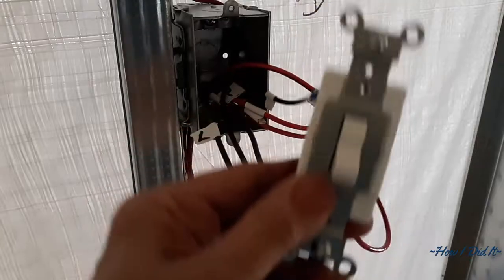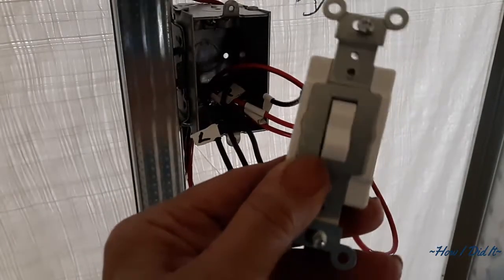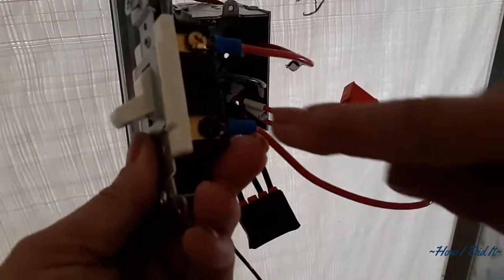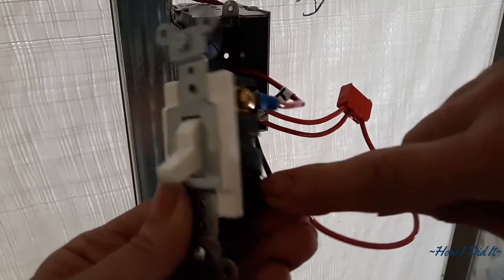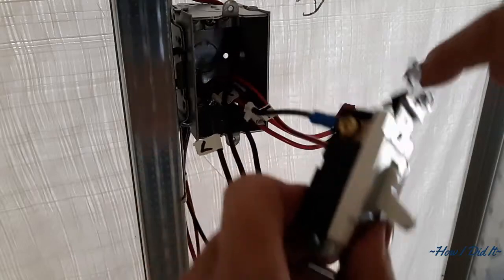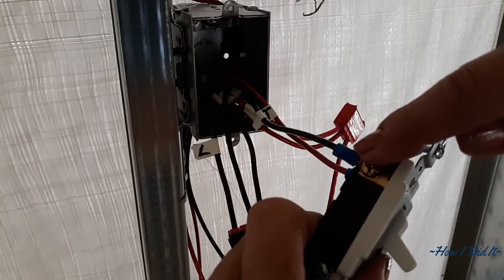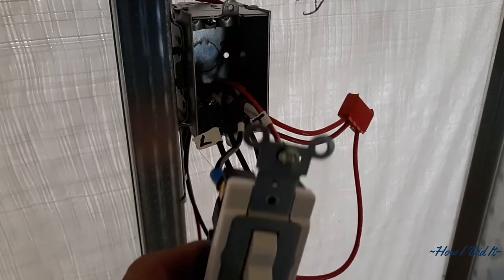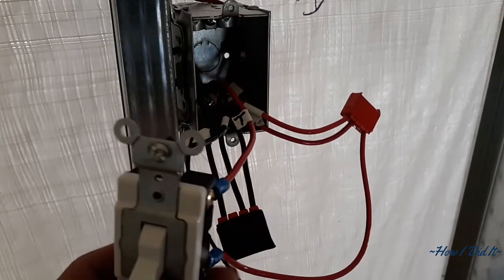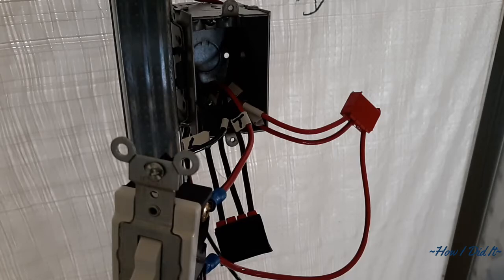When you're wiring a three-way switch, the first switch gets on the black screw, the power, and on the two brass screws, the travelers. The travelers are going to go out to the other light switch. Now, we'll go look at the other light switch.